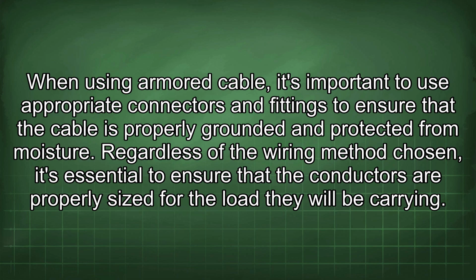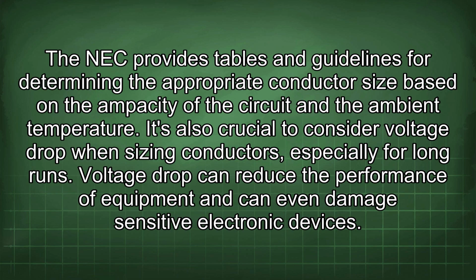Regardless of the wiring method chosen, it's essential to ensure that the conductors are properly sized for the load they will be carrying. The NEC provides tables and guidelines for determining the appropriate conductor size based on the ampacity of the circuit and the ambient temperature. It's also crucial to consider voltage drop when sizing conductors, especially for long runs. Voltage drop can reduce the performance of equipment and can even damage sensitive electronic devices.